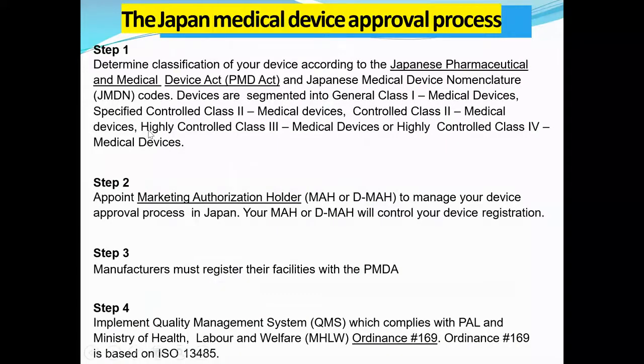So how is the Japanese medical device approval process? First step is to determine the classification of your device according to the Japanese Pharmaceutical and Medical Device Act, which is also called PMD Act, and the Japanese Medical Device Nomenclature, that is JMDN codes. Devices are segmented into general class 1 medical devices, specified controlled class 2 medical devices, controlled class 2 medical devices, highly controlled class 3 medical devices, and highly controlled class 4 medical devices.